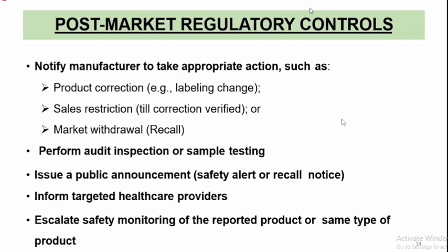mentioning any warning sign on the labels. Then sales restriction till the correction is verified, and if the medical device is causing some serious adverse event, then in some cases market withdrawal can also be done, which is also called recall. Other duties include performing audit, inspection or sample testing, issuing a public announcement, informing the targeted healthcare providers, and accelerating the safety monitoring of these reported products or the same type of products.